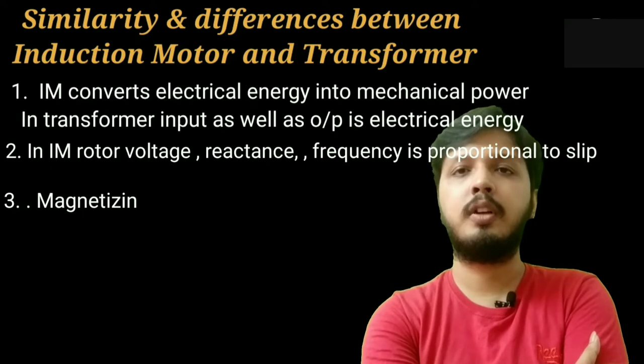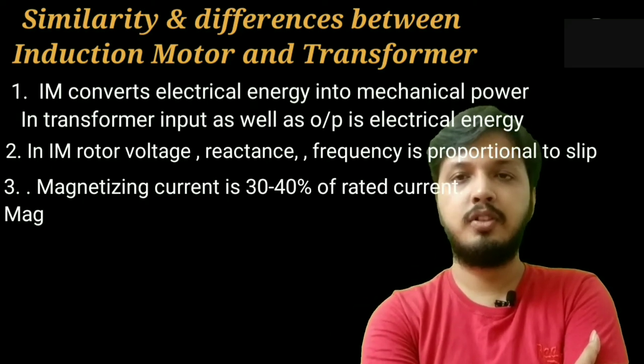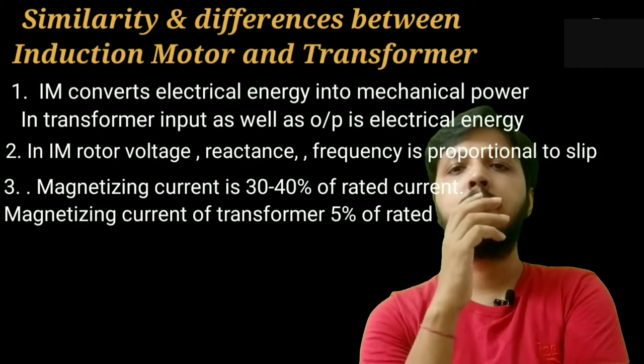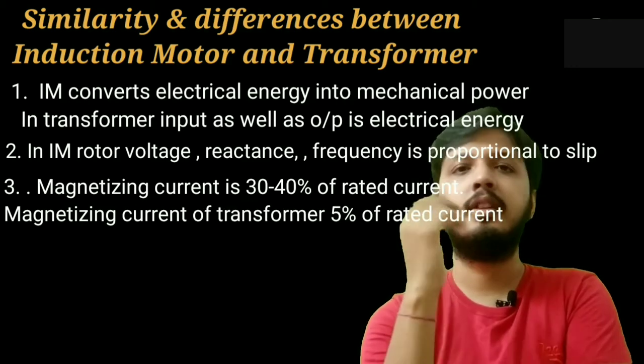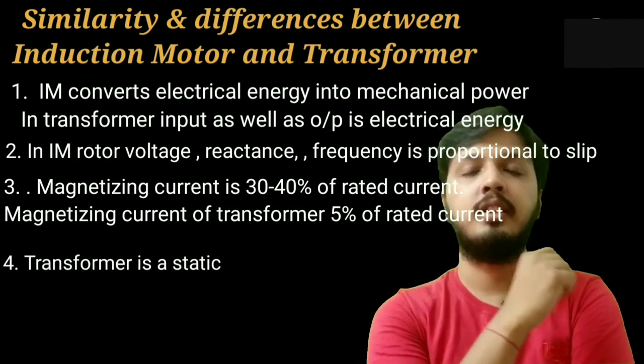Magnetizing current is 30 to 40 percent of rated current in case of induction motor. But in case of transformer, flux passes through the core material. So magnetizing current of transformer is less than 5 percent of the rated current. Transformer is a static device and induction motor is a rotating device.